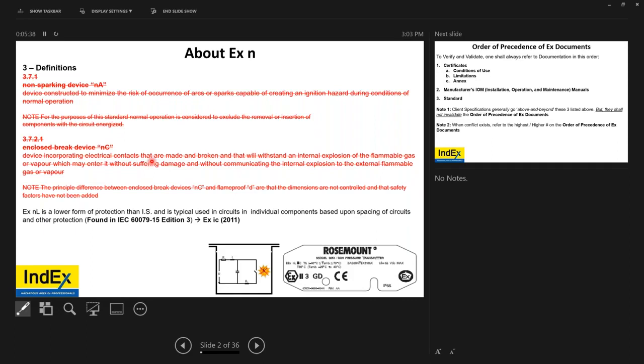Now, EXNL is not found in this edition. It's found in edition 3. So before 2011, EXNL was still used. But unfortunately, the IECEx standards allow up to one edition back. So up until December 2017, people could still technically manufacture EXNL for IECEx use. But for ATEX use, they could not.